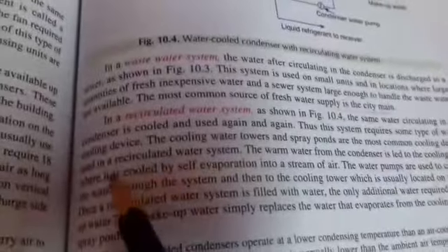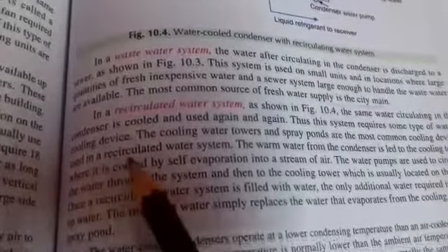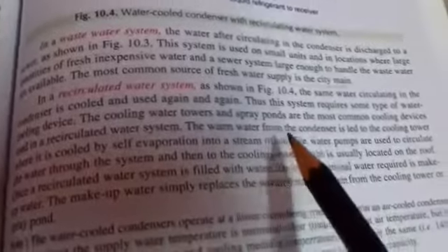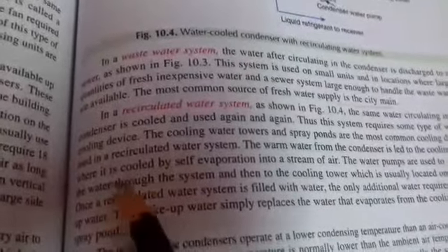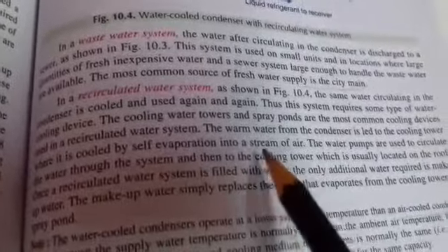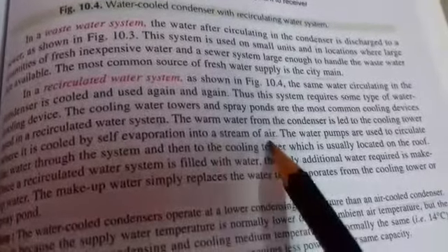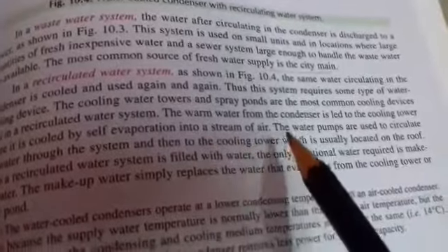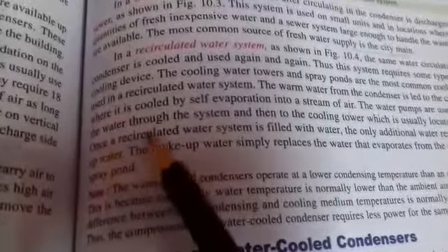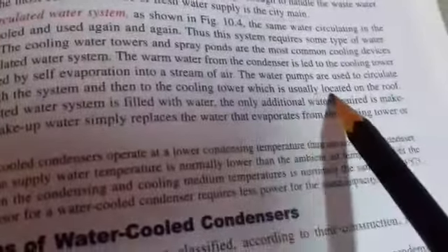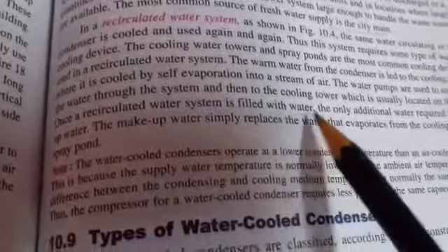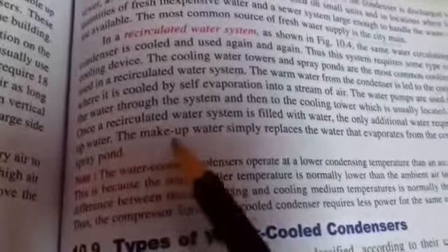The warm water from the condenser is led to cooling tower. It is cooled by self evaporation into a stream of air. It is cooled with the stream of air. The water pumps are used to recirculate the water through the system, and then the cooling tower, which is usually located on the roof. Once a recirculated water system is filled with water, the only additional water required is makeup water. The makeup water simply replaces the water that evaporates from the cooling tower or spray pond.